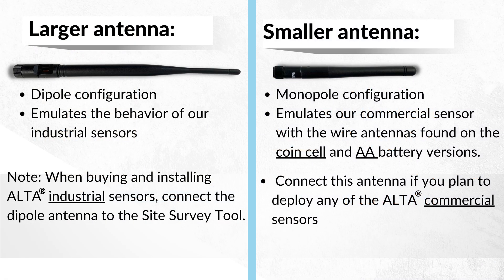You may be asking why the device comes with two antennas. The larger articulated antenna is a dipole configuration and emulates the behavior of our industrial sensors with their external antenna. If you are planning on buying and installing Alta industrial sensors, connect the dipole antenna to the Site Survey Tool. The smaller antenna is a monopole configuration and emulates our commercial sensors with the wire antennas found on the coin cell and AA battery versions. Please connect this antenna if you plan to deploy any of the Alta commercial sensors.